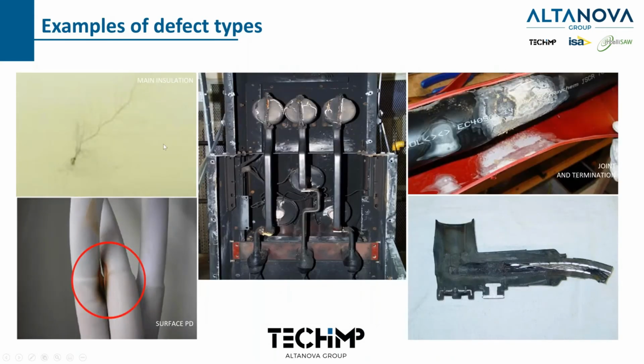All right, so let's take a look at these different types of partial discharge and the damage it does. So on the upper left, you'll see this is an internal discharge. Remember I talked about those water trees back there, caused by water being diffused into the insulation. Well, once partial discharge happens, you get this carbon buildup, and eventually it will fault to ground.